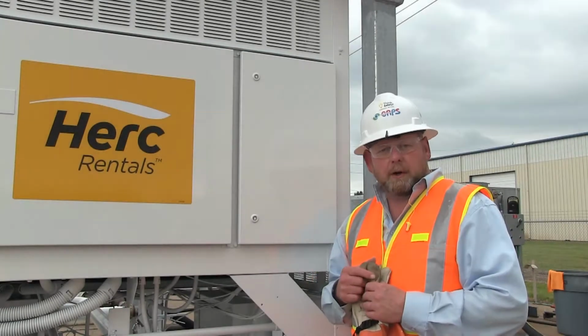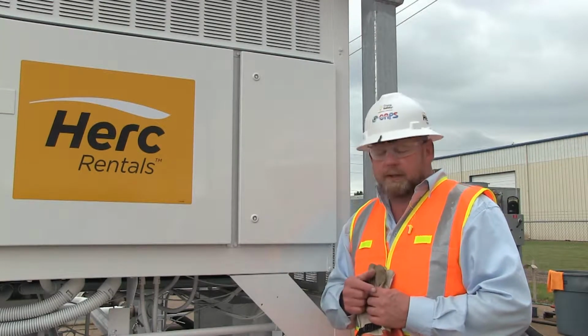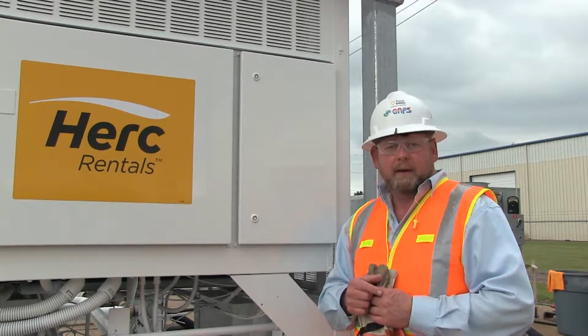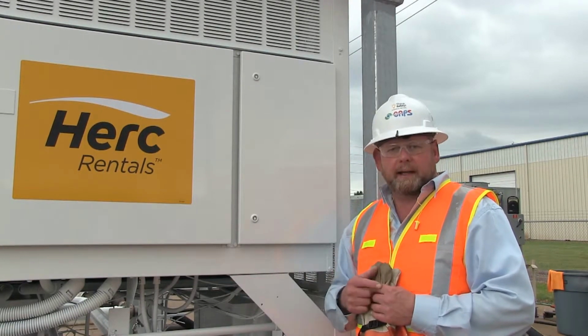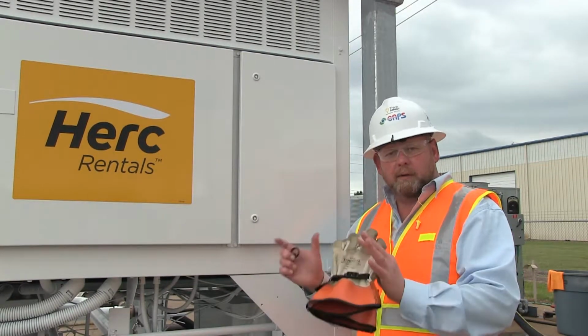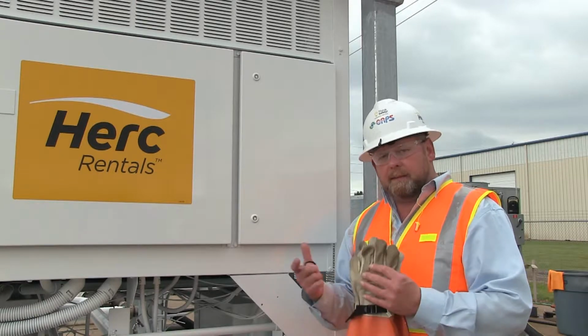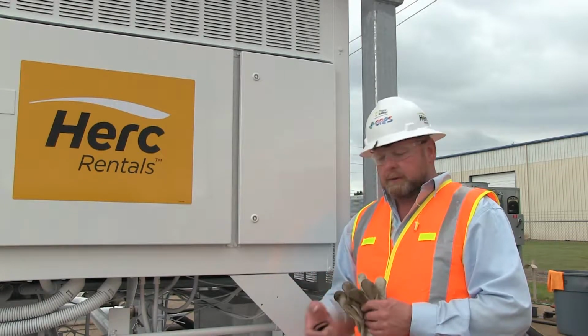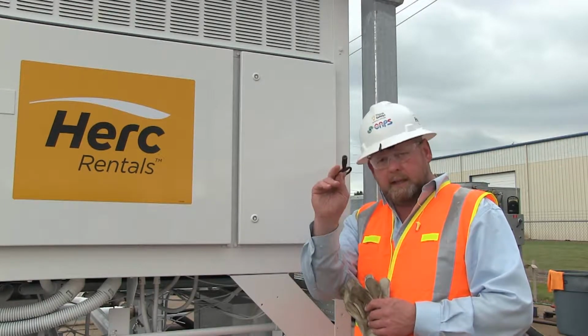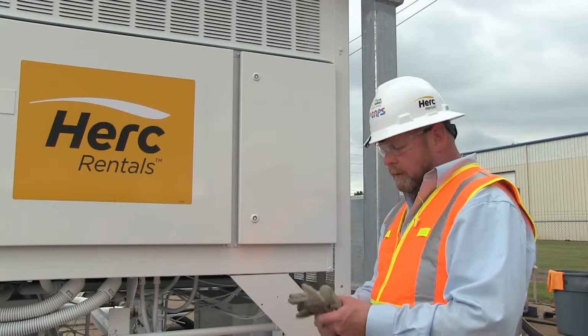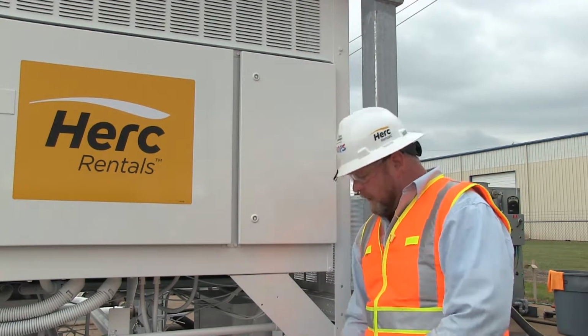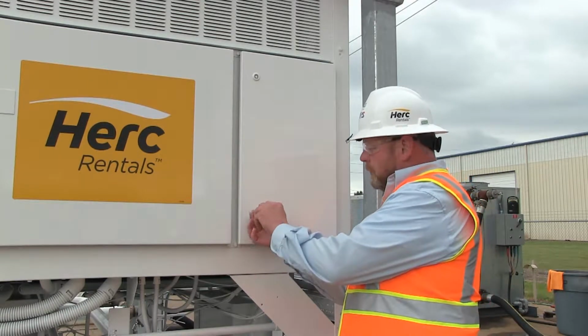Okay, now we're ready to start the chiller up. We've got our crankcase heaters have been on for about an hour and a half. We've got all of our air out, our water circulating, all of our air handlers set, all of our ductwork's done. We've got everything filled up, all the air bled out. So you'll need a security key, one of these keyed security keys to get into the control panel. We don't need our hot gloves anymore because we're done with all the high voltage and sharp edges.